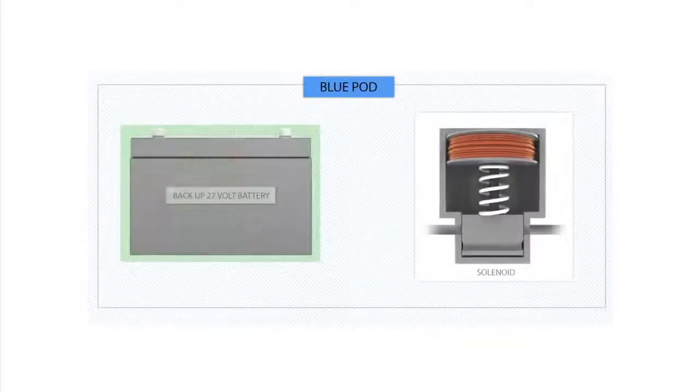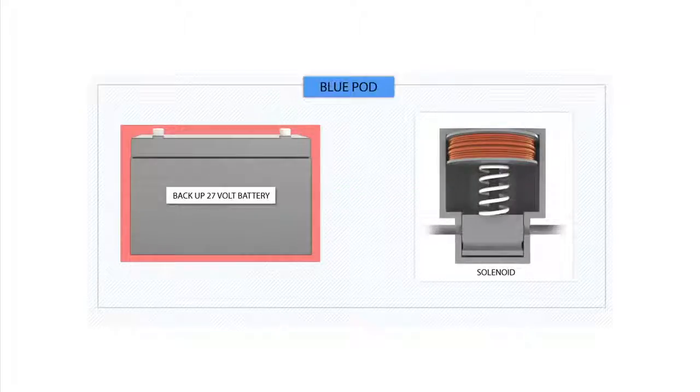However, evidence indicates the Blue Pod had been miswired at some time before the BOP was lowered onto the seafloor. This caused the pod's twenty-seven-volt battery to drain and made it impossible to operate the solenoid valve for the blind shear ram on the night of the accident.